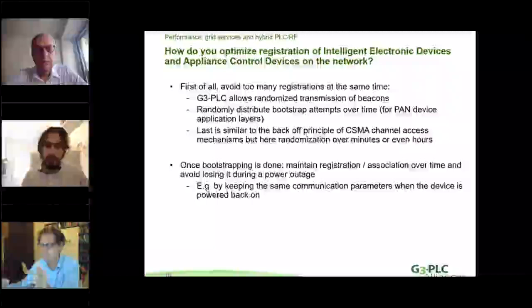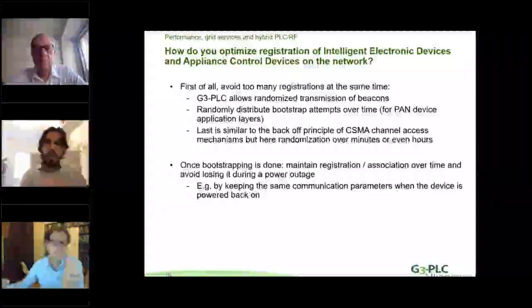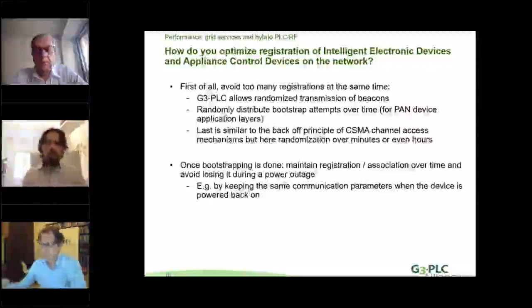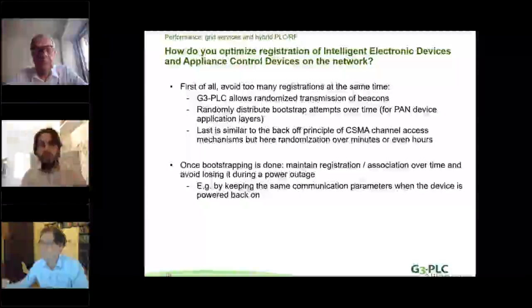It was chosen to do some local processing with the data concentrator collecting all the meters, and then once a day, or whenever needed, the information system connects to the data concentrator and retrieves the data previously collected. And of course, in case you need to do an urgent operation, the information system can ask the data concentrator at any time, so the application process is forwarded to the meter.